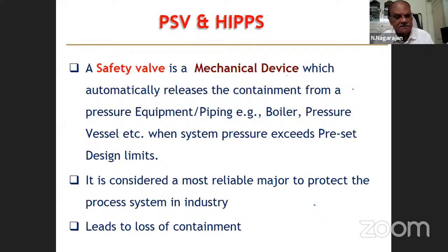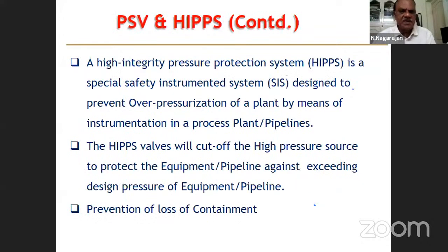Okay. This is more reliable, and this is not acting on any external control signal. This is a mechanical device. It has been found to be the most reliable device to protect the process system. So you will find on all the pressure equipment, you will have the pressure safety valve. It leads to loss of containment, means naturally you have to lose something to safeguard the equipment or unit. You will lose some hydrocarbons to the flare.